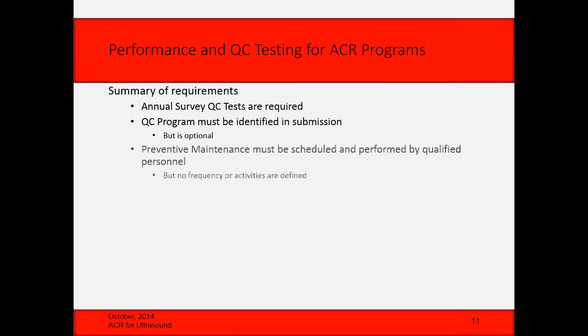And the preventive maintenance must be scheduled, it's not a should, must be scheduled and performed by qualified personnel, but there's no frequency or activities, so you actually have to tell them whether you're going to opt out of this or not. So they do actually allow you to do that, but you must tell them that if that's what you've decided. Obviously, what they really expect to see is you say you're going to do your PMs every 6 months or whatever you've decided is the right time frame and who's going to do it. But they actually do give you a way to say it's not going to, we don't need to do it.